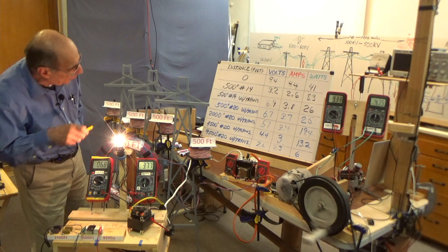That's this line right here, 500 feet of number 20 with a transformer. We're getting 6.8 - today it's a little better than yesterday - 6.8, pretty close to 6.7, and 3.75 here. So we may be getting 26 here, we were getting 27 there - almost the same amount of energy with 1/4 the wire thickness, because there's so few amps moving in the 500 feet. We raised the voltage, lowered the amperage.